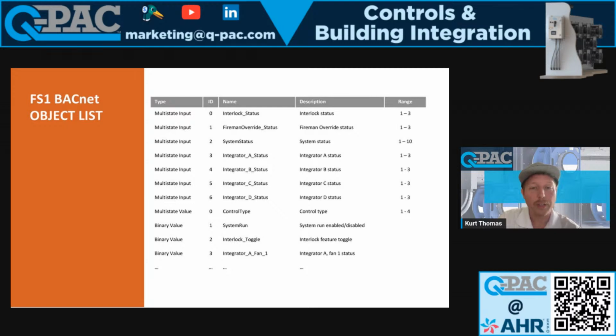Interlock status. So we tell you if you're using the interlock to control your dampers or to do like a lead lag with a return and supply fan, then that'll tell you the status of the interlock. We'll tell you the status of the Fireman Override. We give you a system status, which I'll talk more about later, and integrator status. So integrators, they're quick connect boxes. So do you have an error with your quick connect box? What's the status of it? Most of the time, you're just going to have one quick connect box. If you have more than 9 fans, then you may have 2. Anything more than 18 fans, you may have an integrator C or an integrator D.